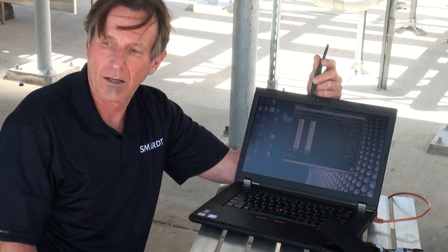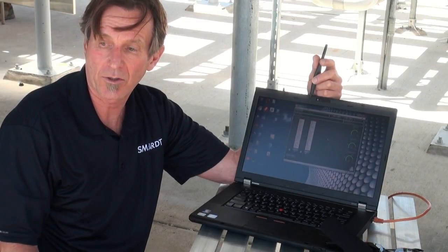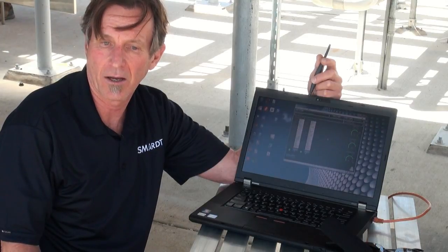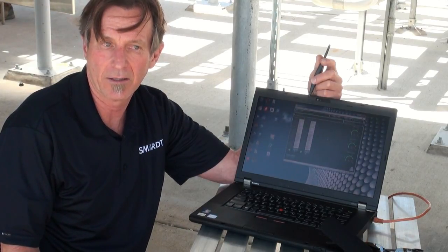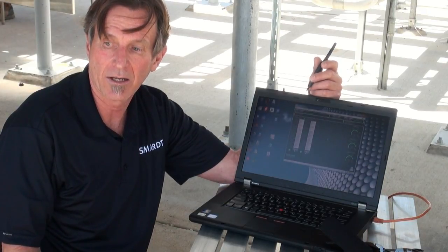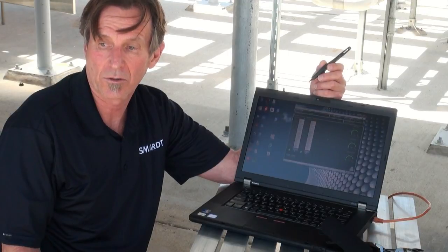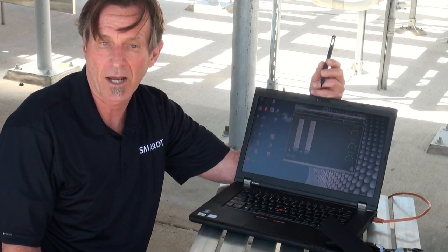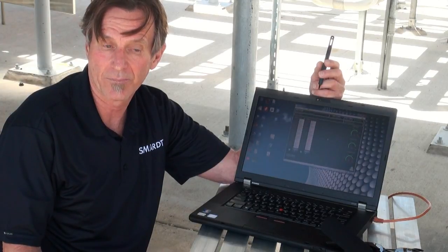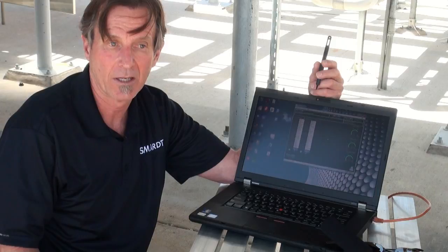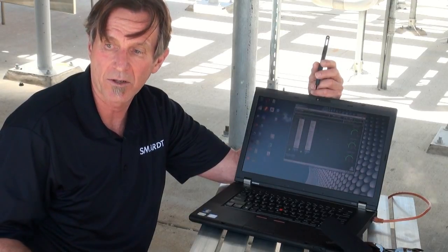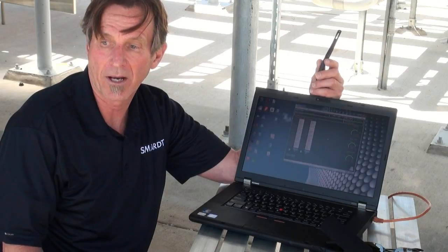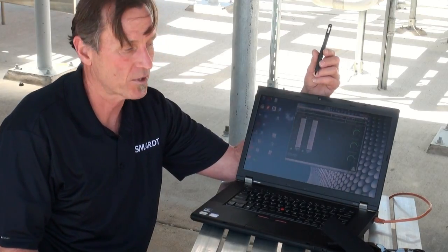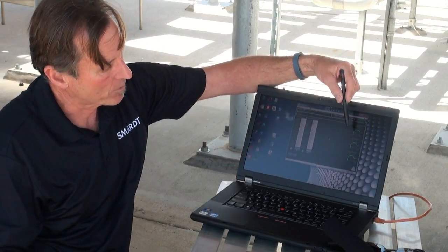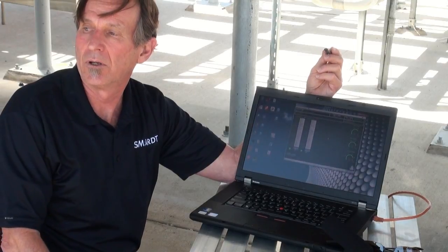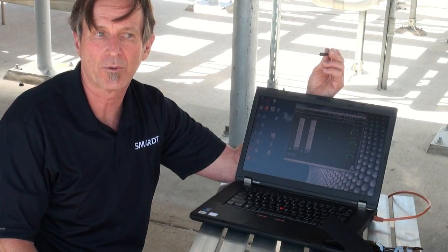What is that speed, do you know? It changes depending on the running conditions. That's part of the lift of the centrifugal, and depending on the condensing temperature and the saturated suction temperatures, those speeds change. Each compressor has its own map envelope that it runs under, and it's been mapped, so it knows at which speeds, under which conditions, you can safely run. So those speeds will change. You'll see the minimum and maximum speed here, and the percent RPM is just the difference between the two. So the higher the percentage on the RPM, the closer you are to choke speed.